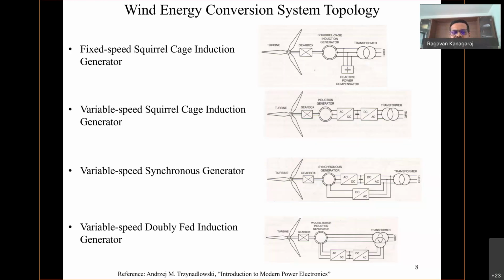Comment on the power electronic converter used in the rotor side in the last scheme. There is no power electronic converter for the stator side. It is directly connected with the grid, and you are putting converters in the rotor side. You want to play with the slip power.